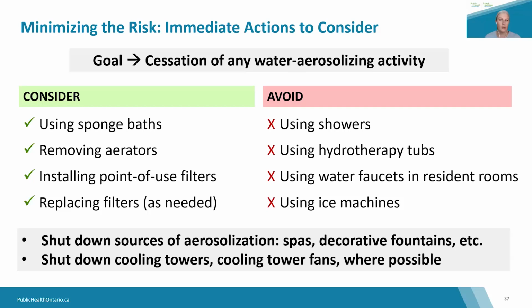So if it's a hot water plumbing or a hot tub or an ice machine, or parts of that system, so a specific wing of a building, for example, that are suspected to be contaminated. This can include shutting off systems until remediation can be implemented. So if a facility's water system is suspected as the outbreak source, the following actions can be taken with regard to water restrictions and control measures while the investigation and definitive management are pending.